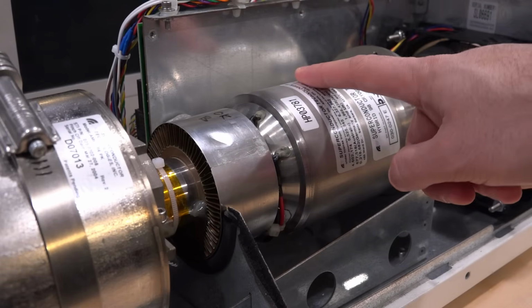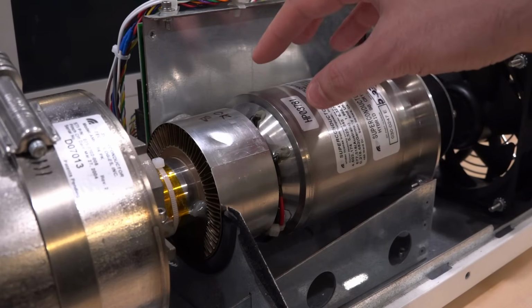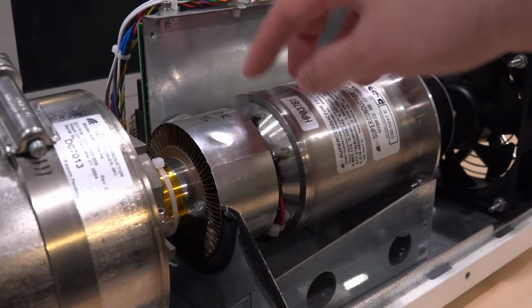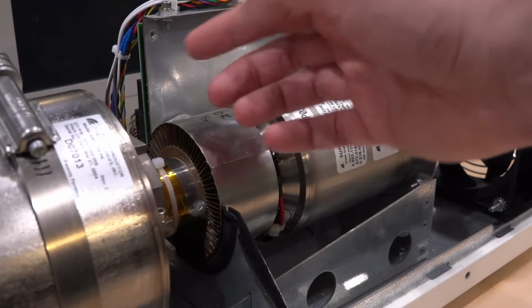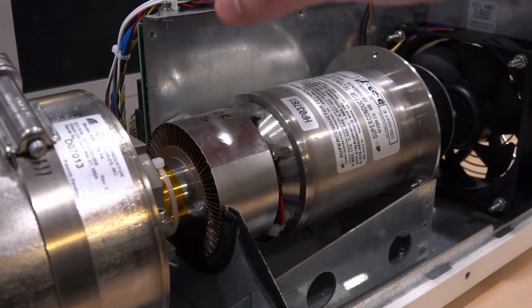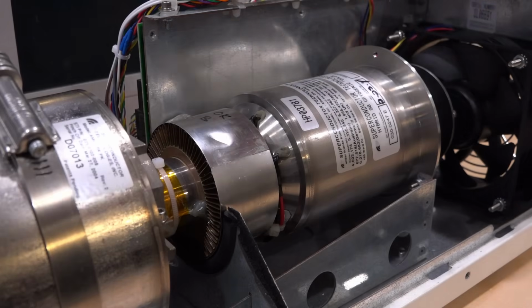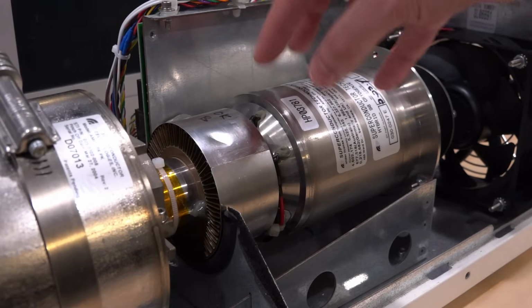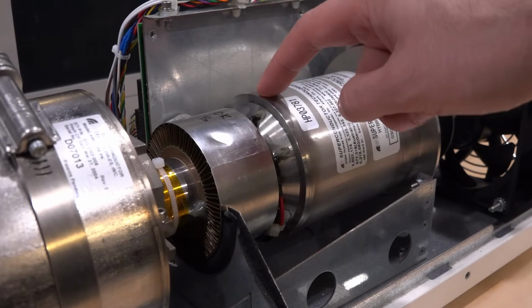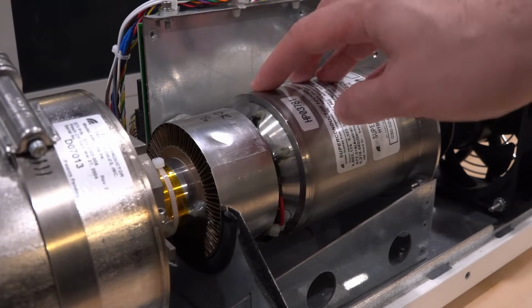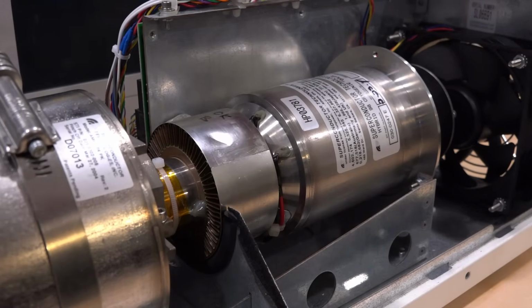Now there's also a few other things. You have to be very careful running these Stirling engines, because how much power you put into them is going to depend on the temperature of the cold tip. Otherwise, you're going to slam that back and forth and actually internally damage this. There's control loops within this that automatically do that, which means there are several temperatures and parameters of this that are controlled by the circuit board, which is on the other side, which I will show you.